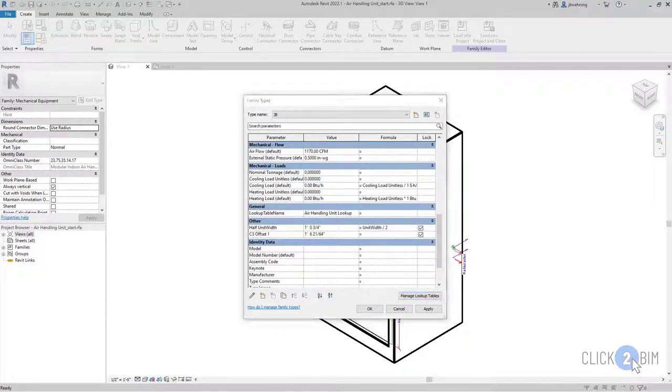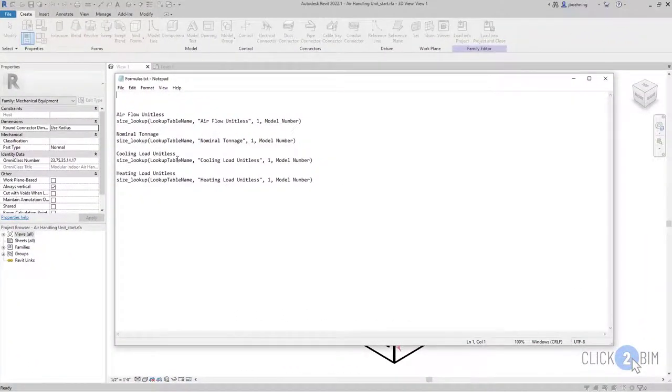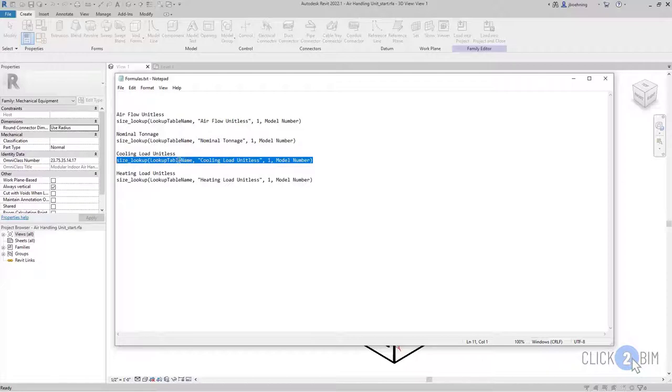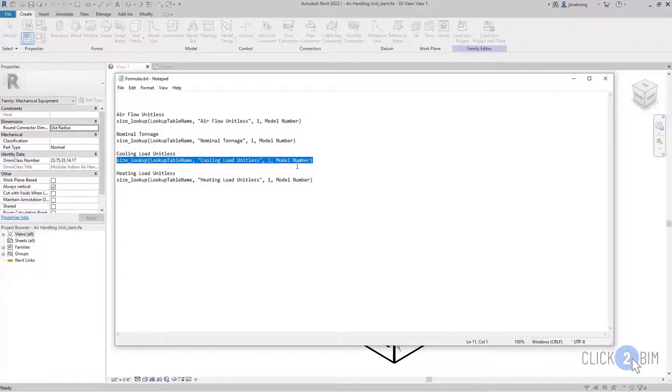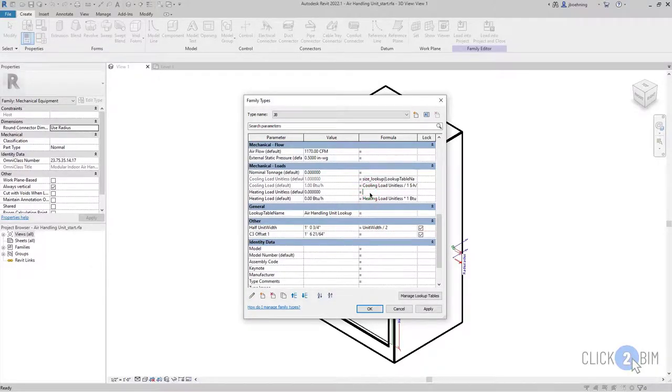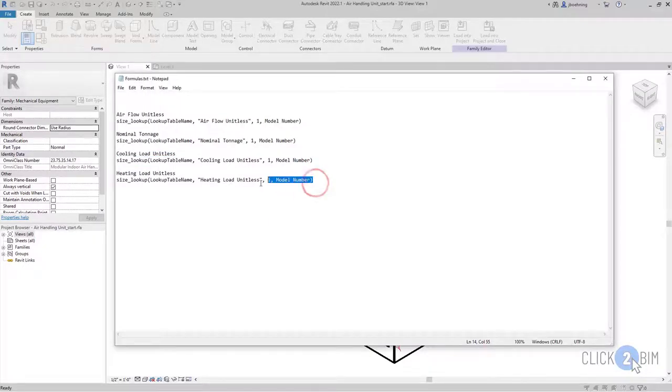And okay, now let me find my formulas again. So now I have the formulas here in Notepad, and once again, I'm going to be calling the lookup table name, which I have that defined in this parameter, and I'm telling Revit to go look in the cooling load unitless column. And if it doesn't find a value, I'm just telling it to put a one in there. That way I know it kind of gives me an idea of what I need to go look for if I see that in a project. And then the model number, so that's what Revit's going to go looking for in that second column. So this was for the cooling load unitless. And then I can do the same thing for the heating load.